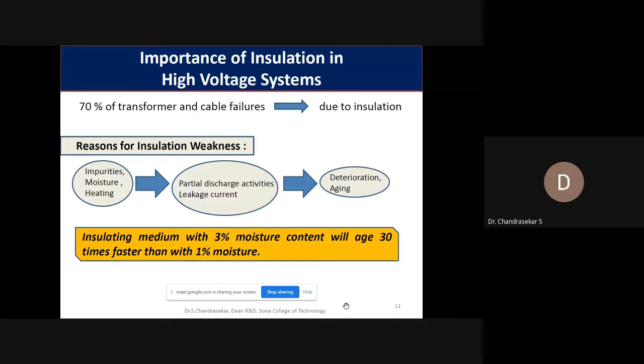As you know, in high voltage systems, 70% of transformer or cable failures are due to the insulation. The reasons for weakness in the insulation are the presence of impurities, moisture, and overheating, along with the many stresses we already discussed. These reasons create partial discharges or leakage current inside the insulation, and it leads to aging and deterioration of the system. You can see that an insulating medium with 3% moisture content will age 30 times faster than with 1% moisture. So it is really remarkable how fast it ages when the percentage of moisture increases slightly. You can see how the environment plays a major role in the degradation of the insulation of these systems.